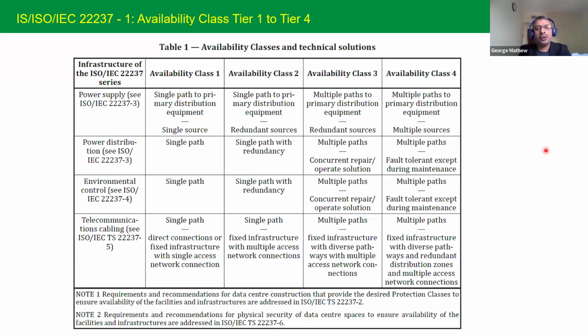Now, cost-wise, we see class 1 is very cheap, then class 2, class 3, class 4, or tier 1, 2, 3, 4. The most expensive one is class 4. In industry practice, what we normally see is that most people are going with class 3 or tier 3, because it is concurrently maintainable, which makes it easy to maintain the load without any disturbance. So I think this is a good explanation.